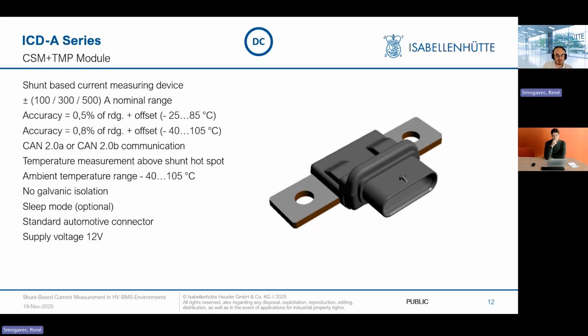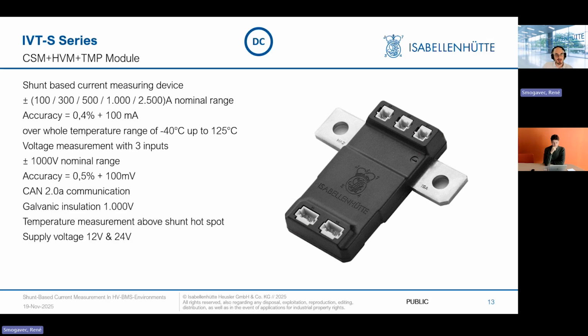But it's probably 50% of what goes in RFIs or RFQs from merely the nominal current range that I personally hear in the daily work. It also features a temperature measurement above the shunt hotspot, directly over it, to ensure a good temperature compensation. It finds its use in PDUs, BDUs, and charging boxes of today's world. The IVTS module does likewise in the same way, but also is used in fuel cells or UPSs, transportation systems, and so on, as one of the two serial production sensors I wanted to showcase to you.